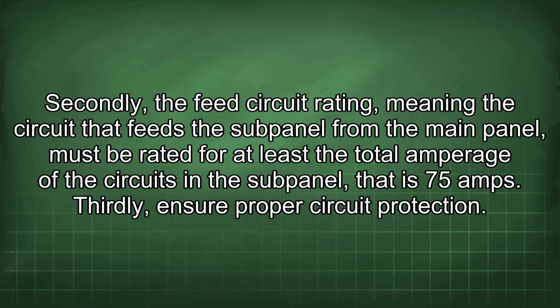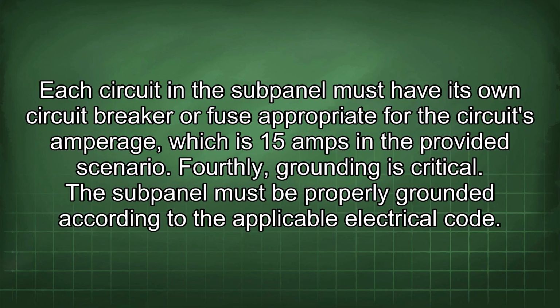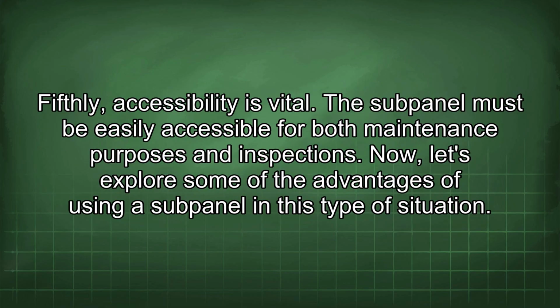Thirdly, ensure proper circuit protection. Each circuit in the subpanel must have its own circuit breaker or fuse appropriate for the circuit's amperage, which is 15 amps in the provided scenario. Fourthly, grounding is critical. The subpanel must be properly grounded according to the applicable electrical code. Fifthly, accessibility is vital. The subpanel must be easily accessible for both maintenance purposes and inspections.